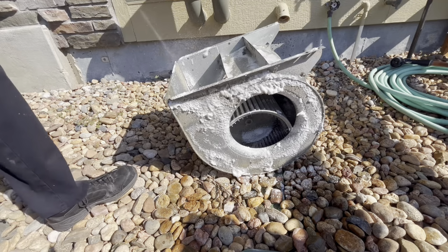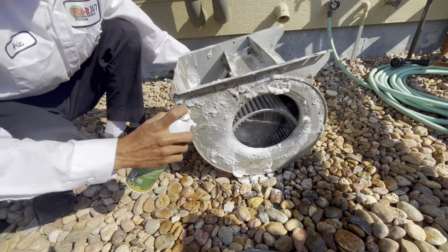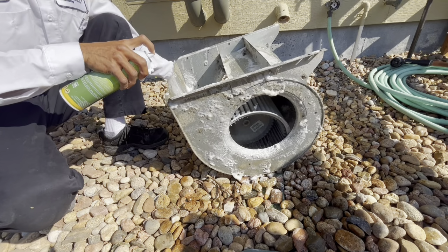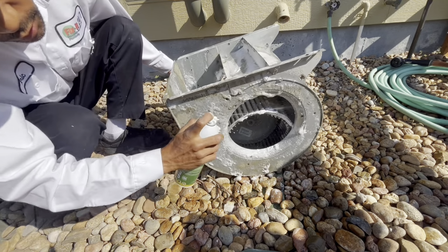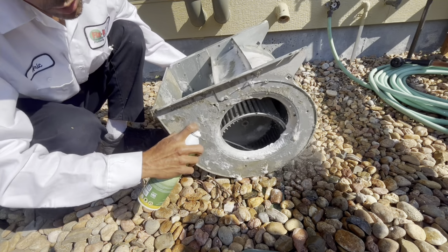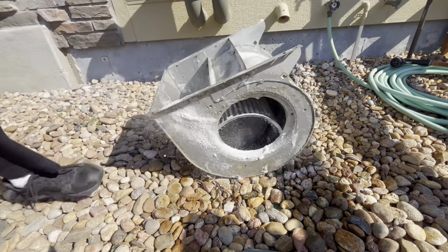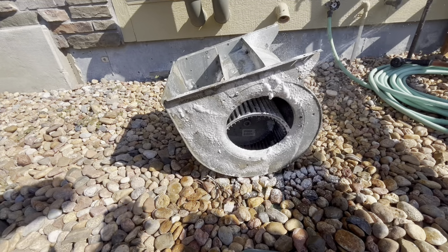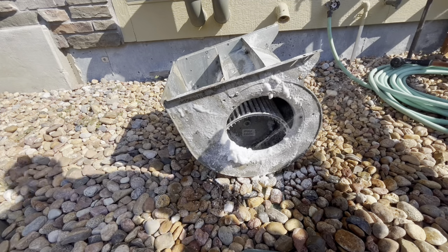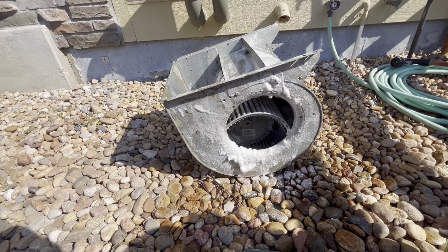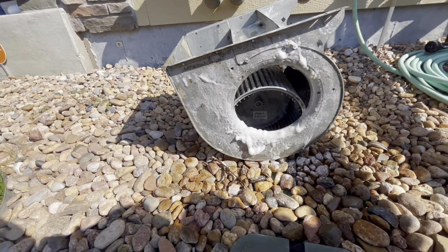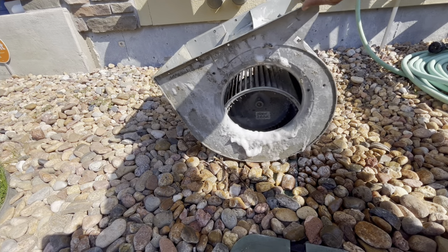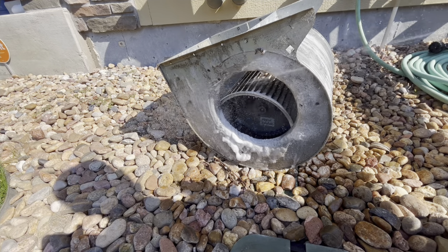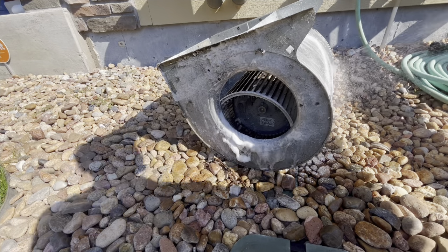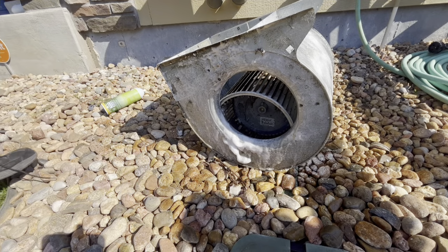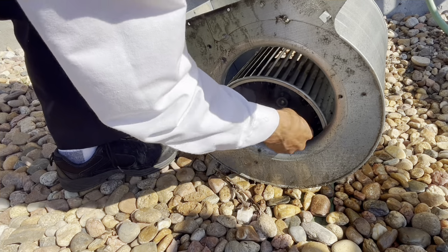If it gets loose in any of the seams where they're connected together, or any of these bolts that are holding it together, it will make noise when the furnace is running. And then it's just best to replace the whole housing and the wheel. And if the motor looks like it needs to be replaced, I recommend replacing that too. Just do all the parts at one time. Basically put in the whole bottom end of the furnace, so that way it works and it doesn't make noise. Because just having a wheel that's off, or a blower motor shaft that's not balanced right, will throw the whole system off. And you'd be surprised.